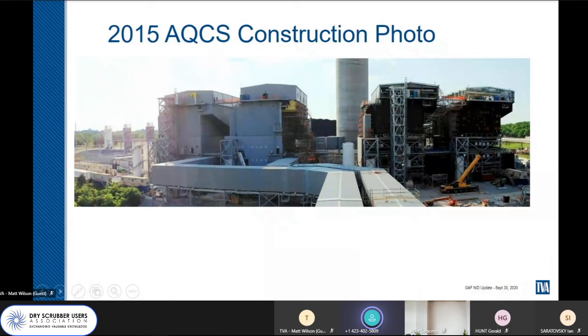Then on the back side, hidden from view, it goes down to our ID fans, and then up to the stack. So each module reactor has a flow nozzle with pressure transmitters on either side, which is tuned to provide flue gas flow measurements. Each unit has 2 day bin reagent silos. That is snuggled in right in between there, in between Alpha and Bravo modules, in between Charlie and Delta modules. Unfortunately, I don't have a terrific picture of that angle. Each of the day bin reagent silos has 2 split variable speed screw trommel feeders on the bottom. So that's what meters the pebble lime flow over to the hydrators. And that metered flow was validated during our performance testing to be accurate enough.